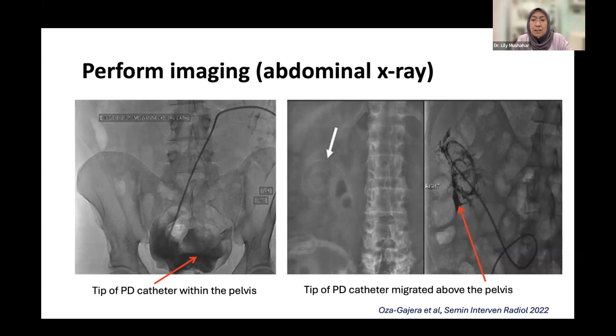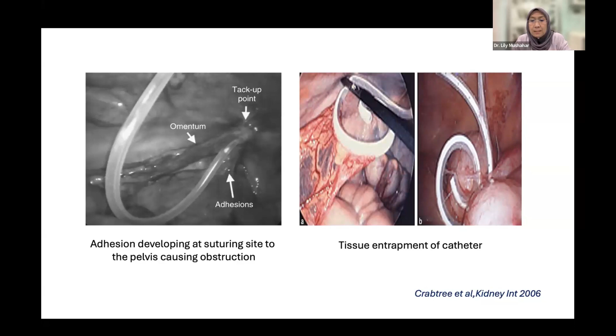And the reason why the PD catheter tends to migrate is either because of the omental wrap, where it pulls up the PD catheter tip and causes entrapment of the PD catheter. Another possible cause is adhesion at the suturing site, which causes obstruction. On the left-hand side, it shows that someone has done an omentopexy, where the PD catheter has been sutured to the pelvis, and this actually caused a tack-up point and obstruction.